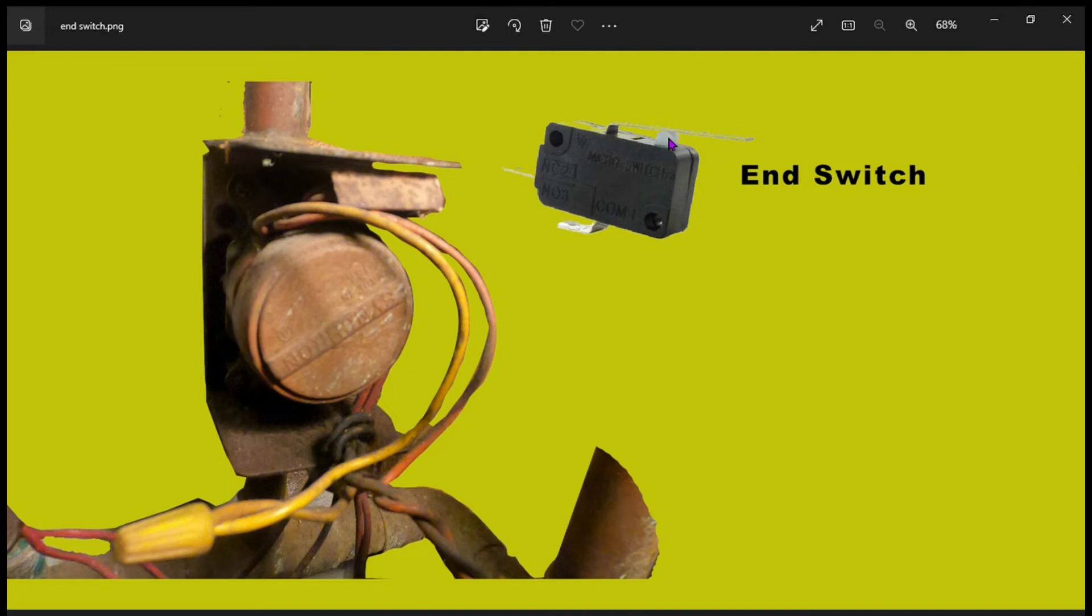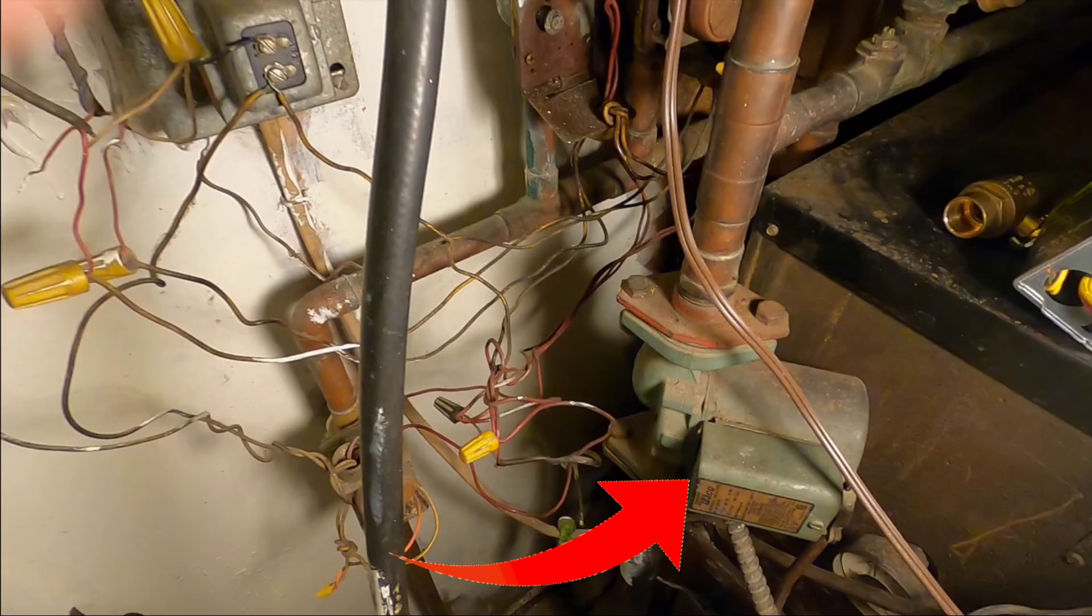This little button over here gets pushed down and the two wires that are connected to it go to the aquastat. Then that aquastat will power the circulator pump which will push the water through the system.